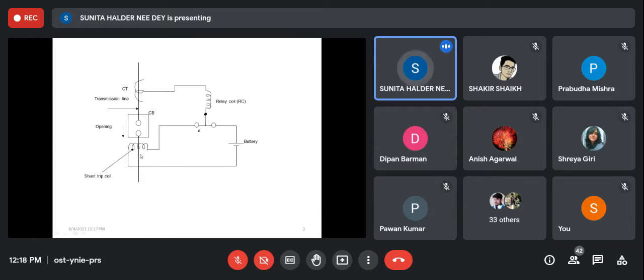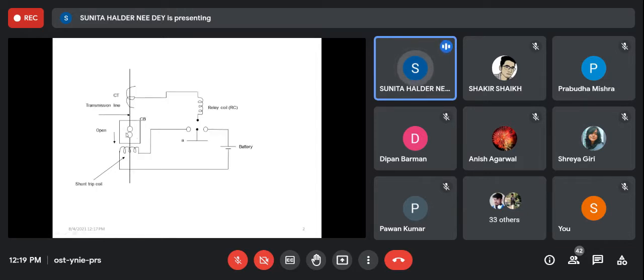So actually, this shunt trip coil will initiate the movement of the circuit breaker. But a circuit breaker is a very heavy device. Can you imagine? It will disconnect a circuit of 2.5 kiloampere. So obviously, it is not a simple contact. It will be heavy material. The contact is not a point. So for the movement of the contact, it may require a motor depending on the size of the circuit breaker. There may be two motors, or the motor should move in the opposite direction depending on the opening and closing operation. And when the circuit breaker is in the closed condition, that means there is one moving contact and one fixed contact. Okay. So when you are moving the moving contact towards the fixed contact, there should be a certain pressure on the moving contact so that it gets full contact with the fixed contact.